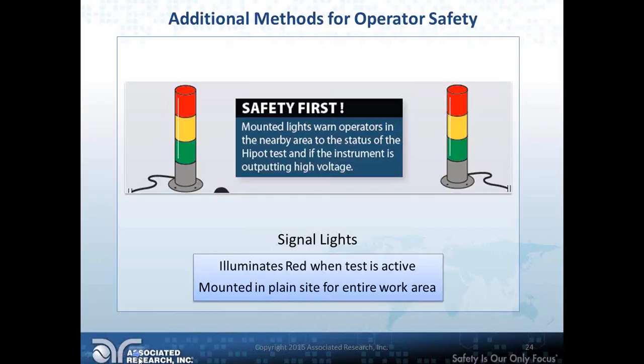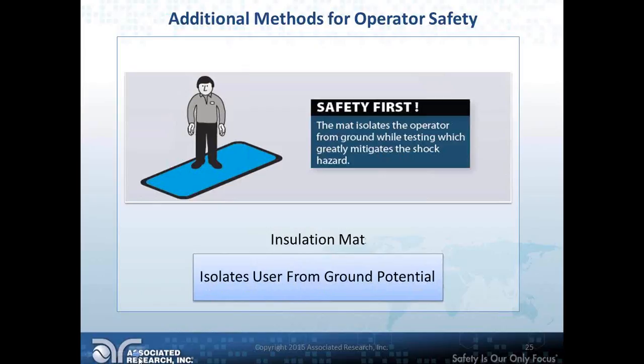Safety mats, insulation mats. If you have a test station where an operator needs to use high voltage equipment, put a mat under them. It's like wearing high voltage boots, just an extra means of protection. It isolates you from ground potential. That doesn't completely negate the hazard. As we showed before, you don't have to be at ground potential for there to be a shock hazard, but it helps.